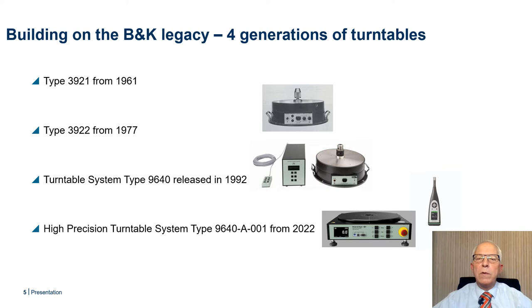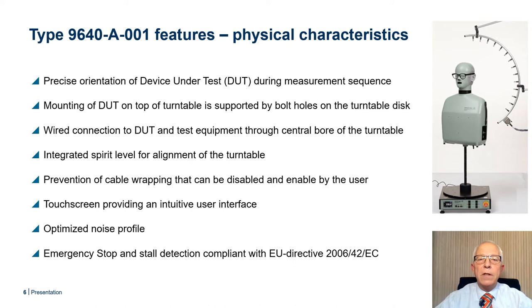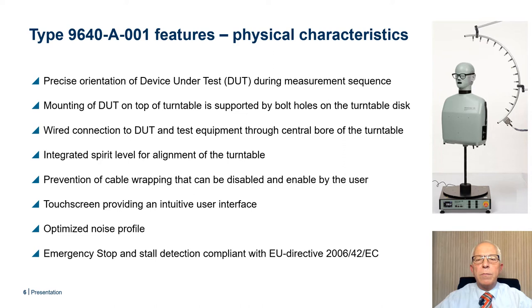This new high-precision turntable is shown side-by-side with the newest sound level meter, as the two instruments share user interface design concepts. The turntable allows precise positioning of the device under test during a measurement sequence. It is also possible to mount various devices on the turntable utilizing the bolt holes on the desk. Wires for connections to the device being tested or the test equipment can be led through the central bore of the turntable. For proper alignment, an integrated spirit level is provided. Prevention of cable wrapping is implemented and can be disabled and enabled by the user.